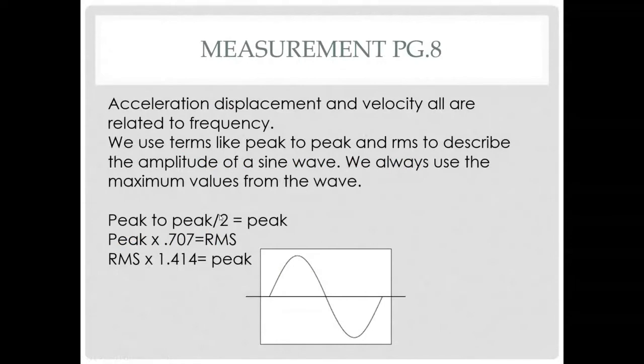Acceleration, displacement, and velocity are all related to frequency. We use terms like peak-to-peak and RMS to describe the amplitude of a sine wave — those of you who are electricians are very familiar with this. We always use the maximum values from the wave. Frequency is measured from one peak to the next. The peak value is our peak displacement, and peak-to-peak is from the top of one peak to the bottom of the other. To convert from peak to RMS, multiply by 0.707; to get peak from RMS, multiply by 1.414.